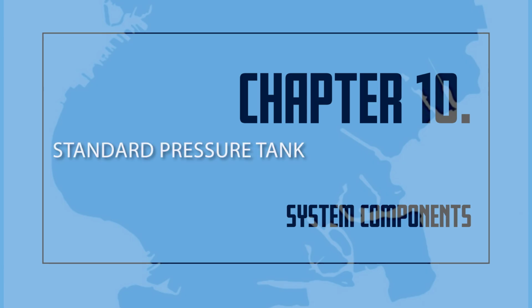Standard pressure tank. Pressure tank alarms. All pressure tanks used to provide the required primary water supply for a sprinkler system shall be equipped with 2 high and low alarm systems. One system monitors the high and low air pressure. The other system monitors the high and low water levels.